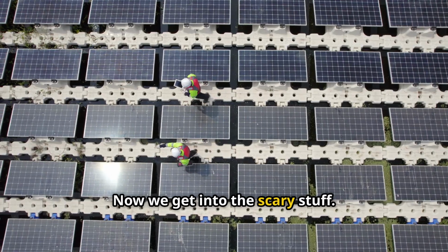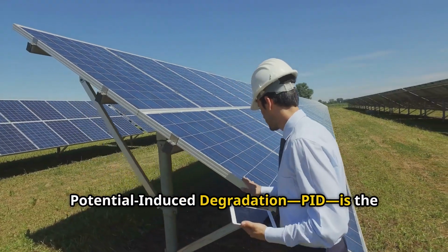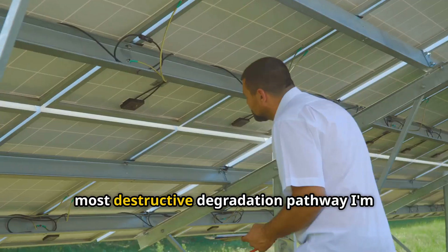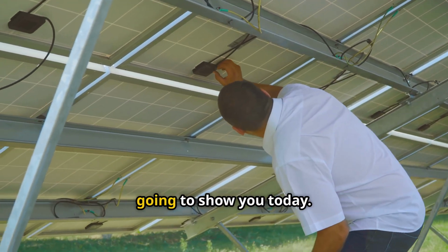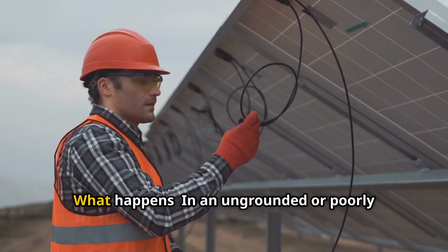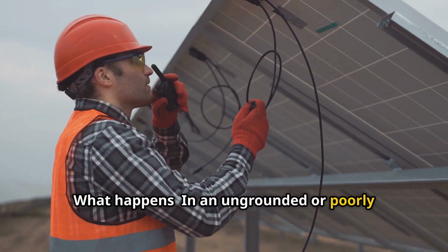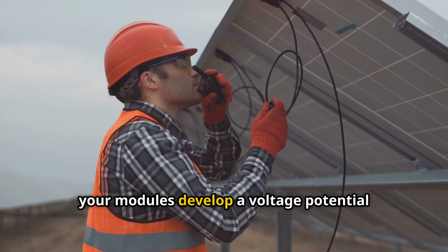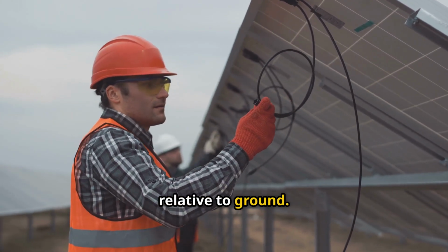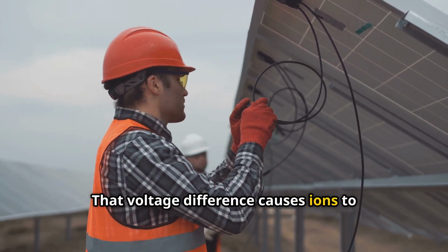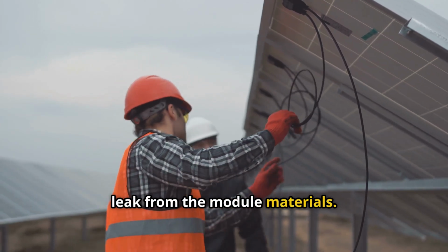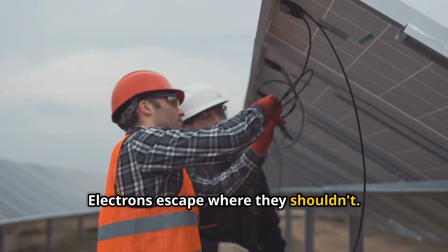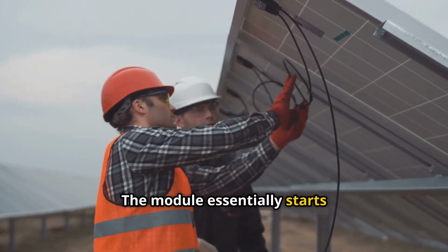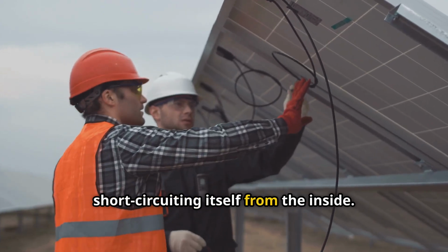Now we get into the scary stuff. Potential induced degradation, PID, is the most destructive degradation pathway I'm going to show you today, and here's what makes it terrifying. It's invisible until it's already destroyed your equipment. What happens? In an ungrounded or poorly grounded solar system, your modules develop a voltage potential relative to ground. That voltage difference causes ions to leak from the module materials. Electrons escape where they shouldn't. The module essentially starts short-circuiting itself from the inside.